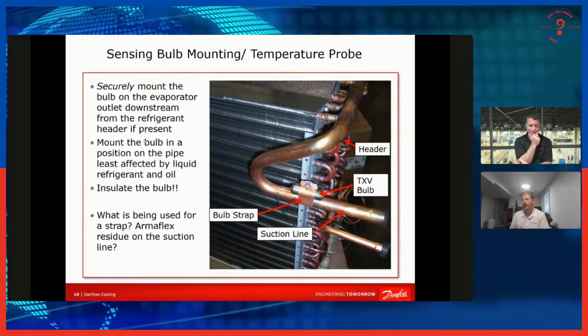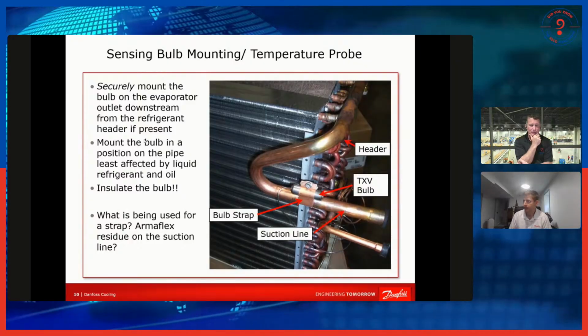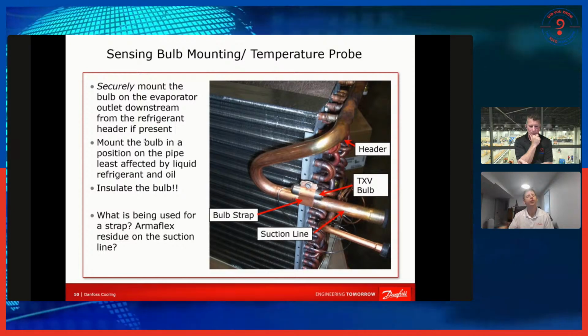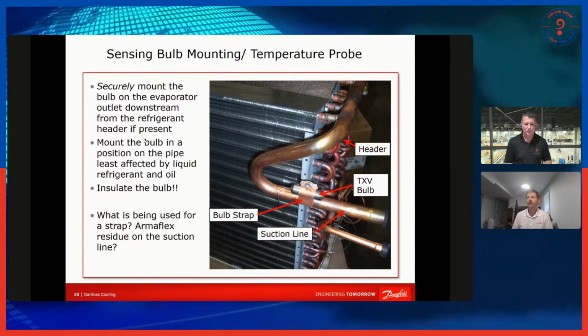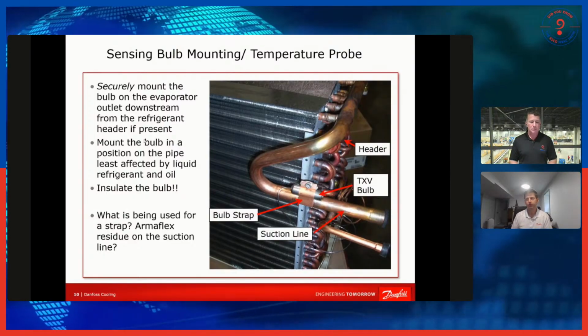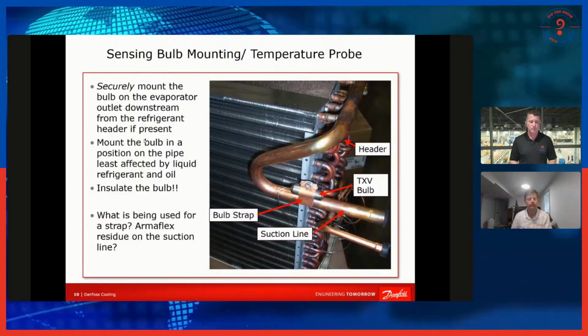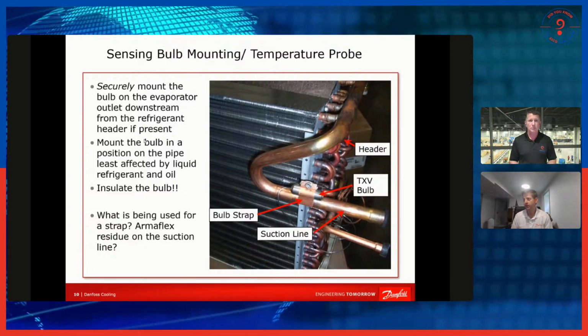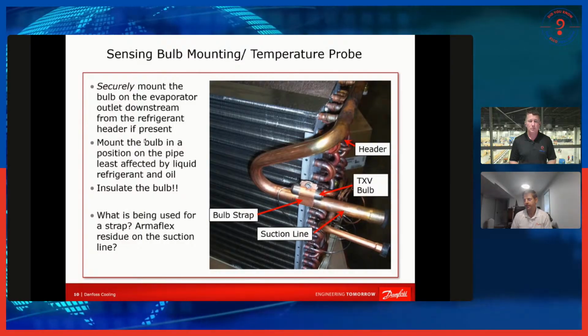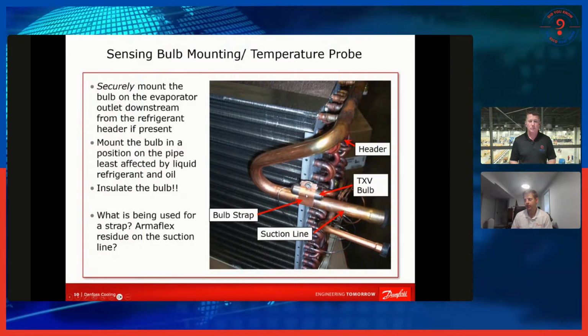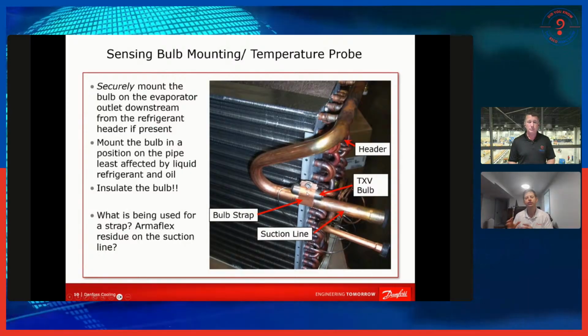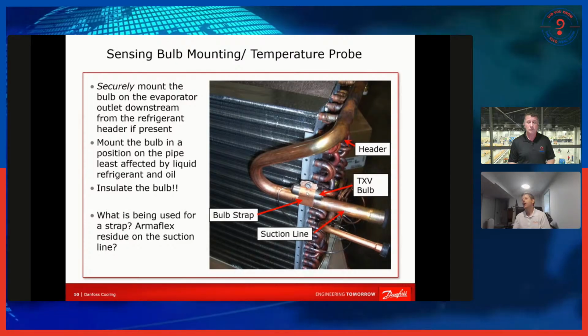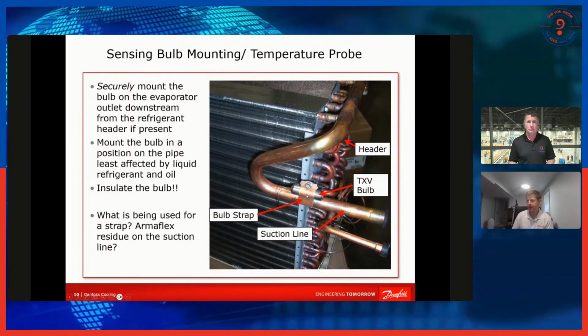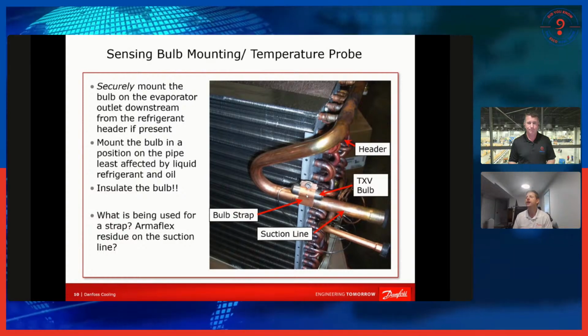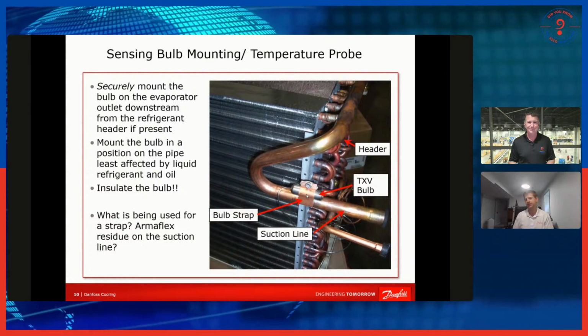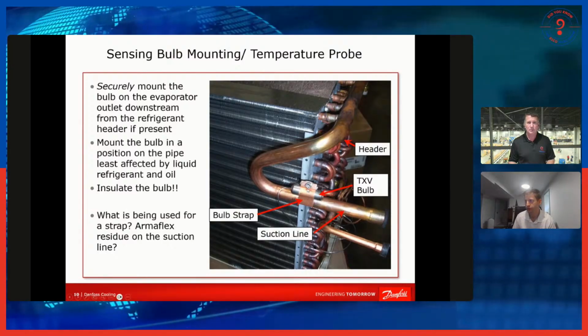Sensing bulb location versus a temperature probe to an EXV controller. They perform very similar functions, and in general, they should be mounted in the same location. So when troubleshooting, we kind of referenced this earlier, it's important to check it out. For a TXV bulb, it's important that it's strapped down. There's a good strong bulb strap giving it a good connection. Copper is better than a hose clamp, but a hose clamp can still do a pretty good job. Both of those are way superior to a zip tie. Zip ties, especially for a TXV bulb, don't do a great job.